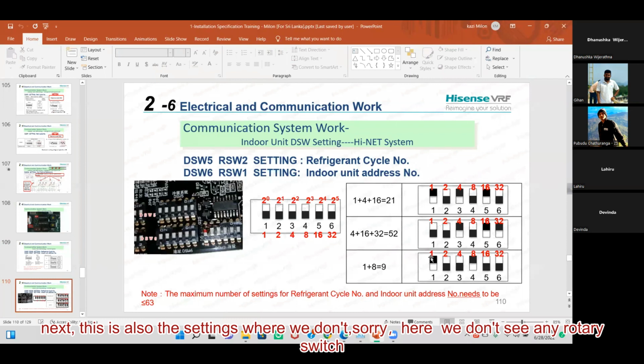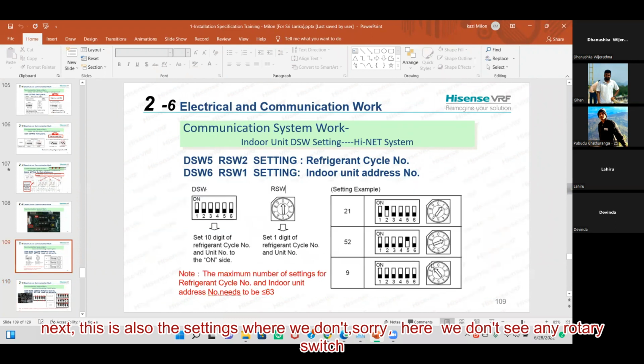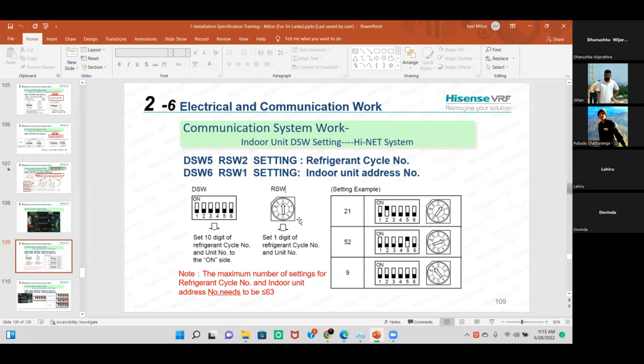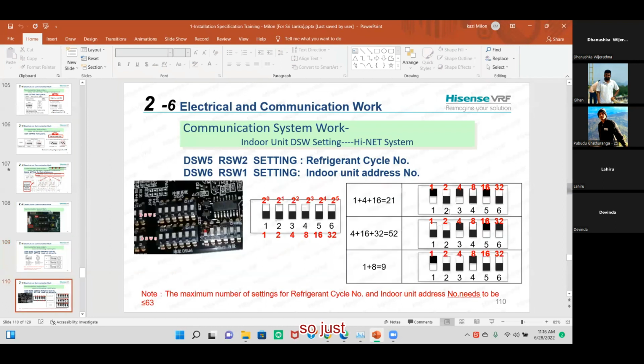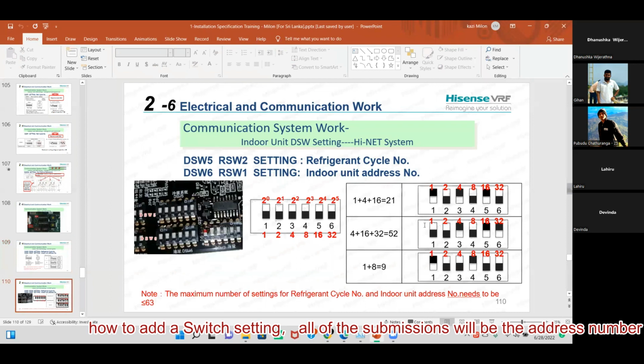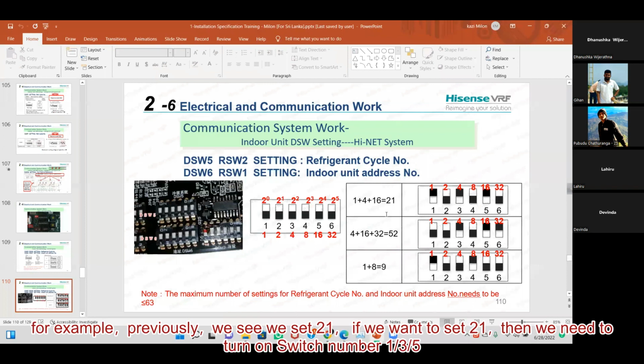Next, this is also address settings, where here we don't see any rotary switch in our unit. Then we use the switches. You can see here how to address it. The sum of all the switches will be the address number. For example, previously we saw here we set 21. If we want to set 21, then we need to turn on number 1, turn on number 3 and also turn on number 5.